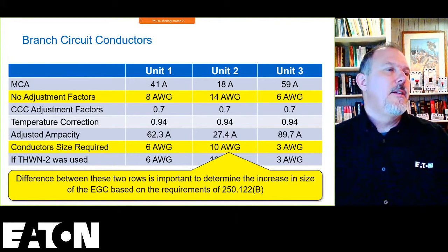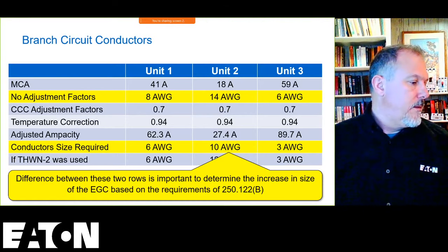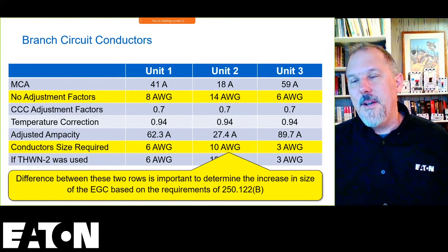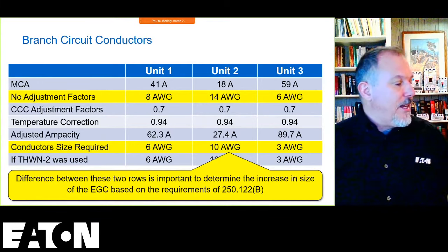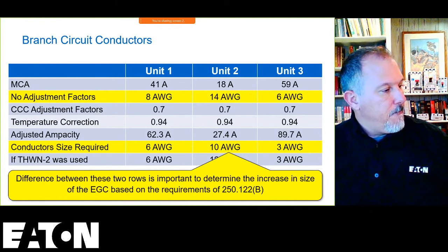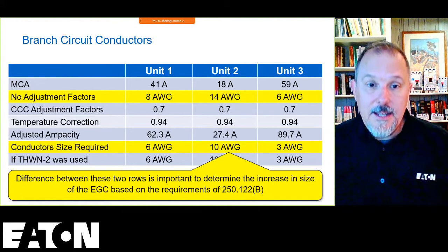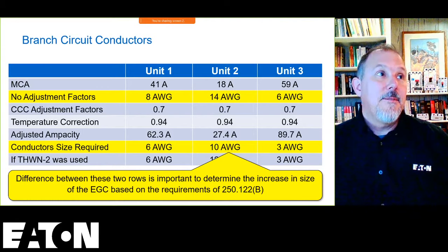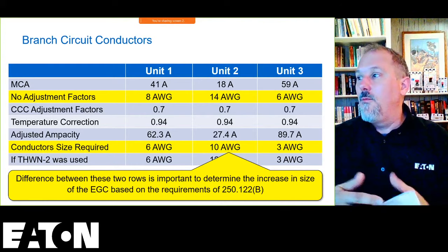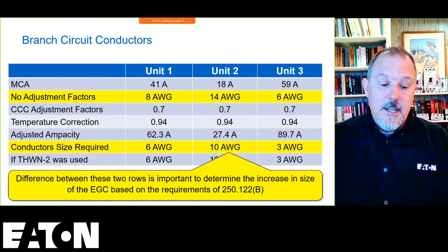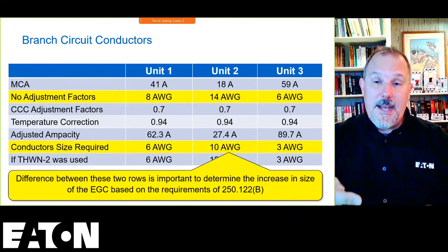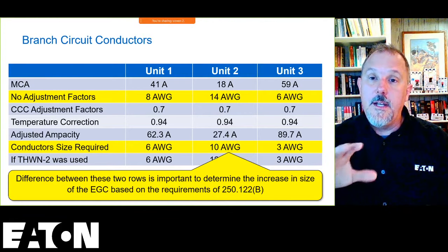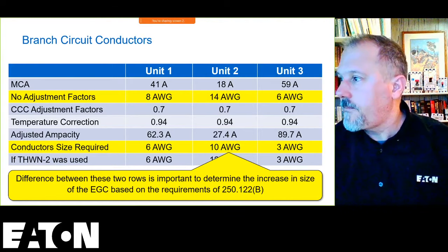If you're adjusting the conductor ampacity, that is the minimum size conductor. Oh, I don't know about that, Don. You might be right there. I see what you're saying. So what Don Ganier is saying, and I think what you're saying, Ryan, is if I look at the 17 code, it says increased in size from the minimum size that has sufficient ampacity for the intended installation. And ampacity is based upon conditions of use. Right. So because it's based on conditions of use, I would not have to increase the size of the equipment grounding conductor, because my conditions of use include the ampacity adjustment based on temperature and the adjustment based upon numbers of current carrying conductors. Good point, Don and Ryan. Thanks. All right.